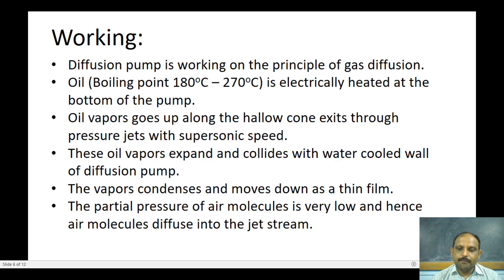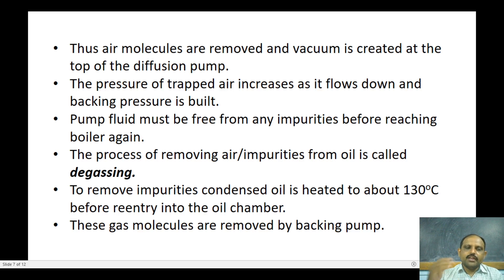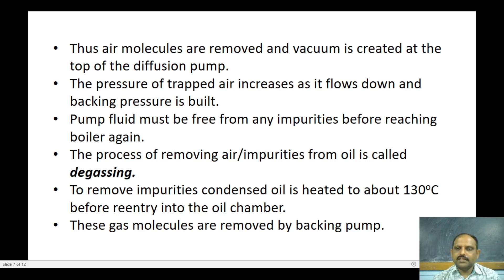The partial pressure of the air molecules is very low, so the air molecules diffuse into the jet stream — the oil vapor. The air molecules combine with the oil vapor and come down with it, thus removing the air molecules and creating a vacuum at the top of the diffusion pump.